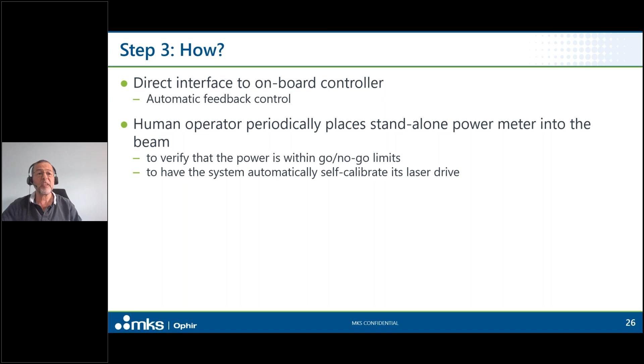A specific but very common answer to steps 2 and 3 is to use a custom designed or custom modified OEM sensor built into the system. Laser-based surgical systems, for example, generally have regulatory requirements to have an integrated measurement capability. The huge plus of this is that it gives you exactly what you need. It would be configured exactly for this system, for that laser power, wavelength, et cetera. On the other hand, because we're talking about at least some degree of customization, it would only make commercial sense if there's going to be some kind of series production. This wouldn't make sense for either the user or the supplier if it's only going to be a one-off or something like that.